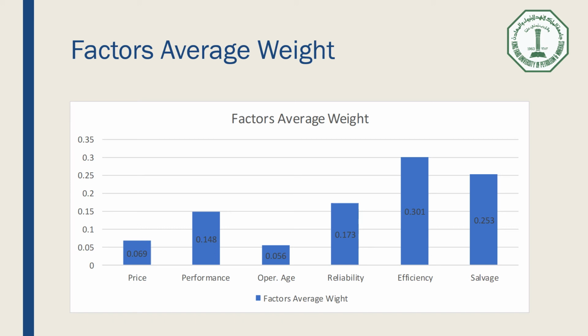Salvage value comes as the second most effective factor with around 25%. Transformer salvage value increases as it has more copper. Usually, the salvage value for a typical transformer that weighs around 3,000 kilograms varies between 3,000 Saudi Riyal and 40,000 Saudi Riyal, which is a good amount of money that the organization or company can benefit from.